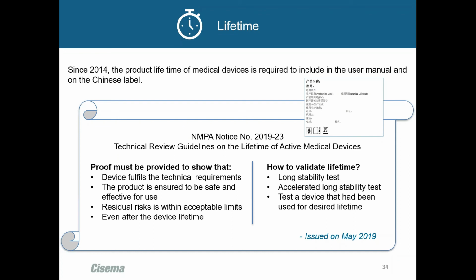And in May 2019, the NMPA updated the technical review guidelines on lifetime. And this poses a new challenge for a lot of registrants of especially active medical devices, actually. So here important is that you have to prove that your product is still safe and effective to use until or even beyond the device lifetime. And you can do this in form of a long stability test, an accelerated long stability test, or by testing a device that had been used in the market for a long time, such as 10 years or so.